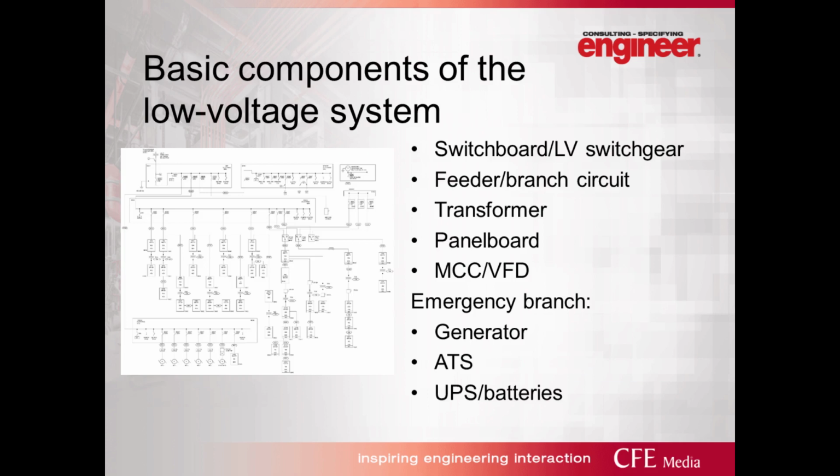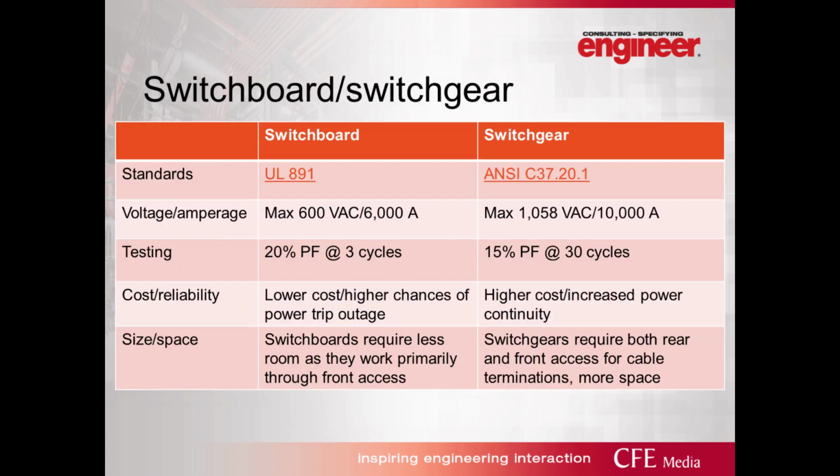I mostly will be focusing on the basic components of the low voltage system, main codes, standards, and common practices when it comes to specifying or sizing these components. Let's start with the switchboard versus low voltage switchgear. A lot of times these two terms are used interchangeably. However, these two terms are technically different.